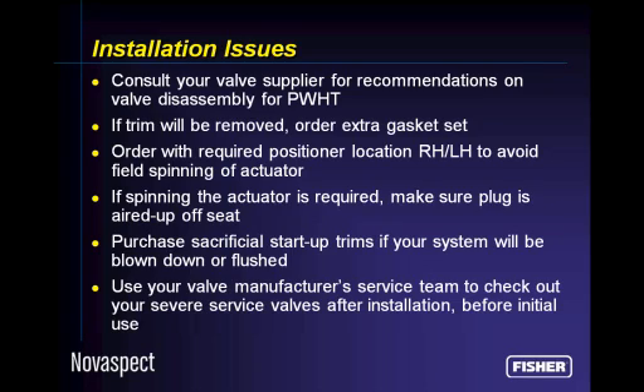Even if we mess this up, or you mess it up, you're going to be compelled to want to spring the actuator. I'm sorry, rotate the actuator, spin it around so that the positioner ends up on the side that you want it. Do not do that with the plug on the seat. You're just going to score the plug, and we're going to get a bad shutoff. So if you've got to do that, if it's a fail open valve, you're okay. The plug is off the seat. If it's a fail closed valve, you've got to put air in the actuator to raise the plug off the seat. Then you can spin the actuator. Then you can take the air off, and you're okay.